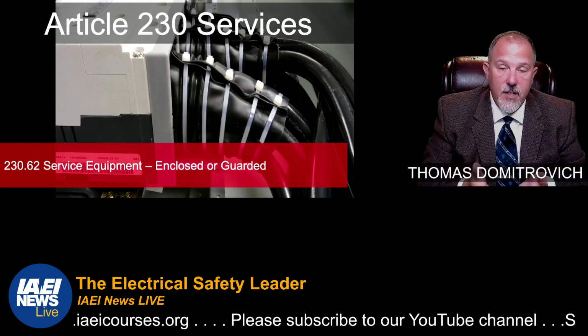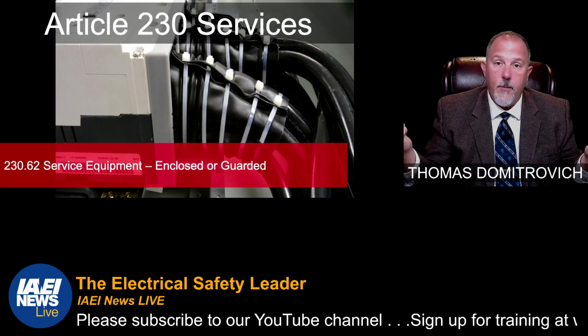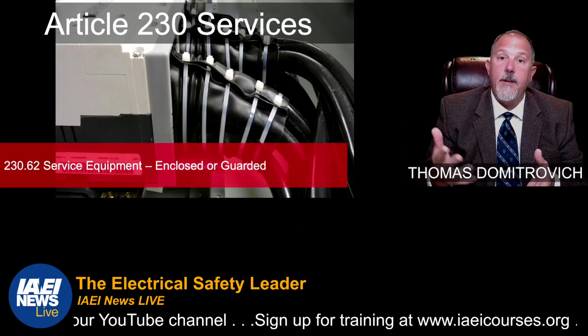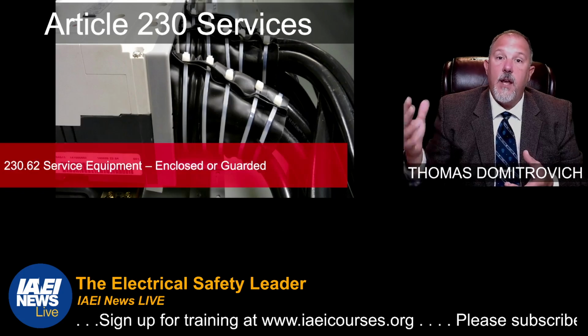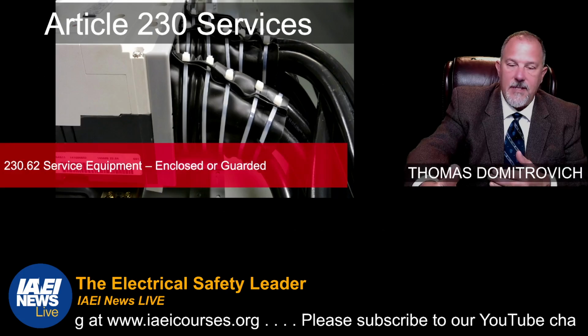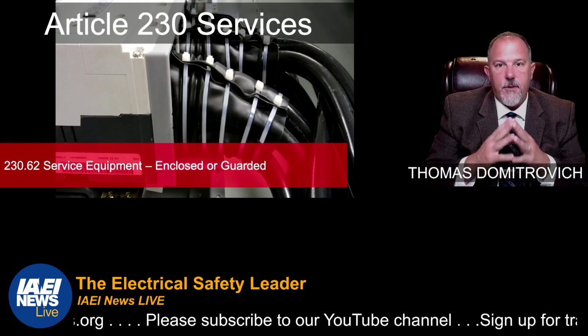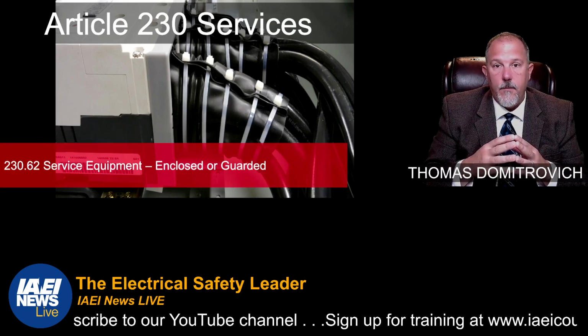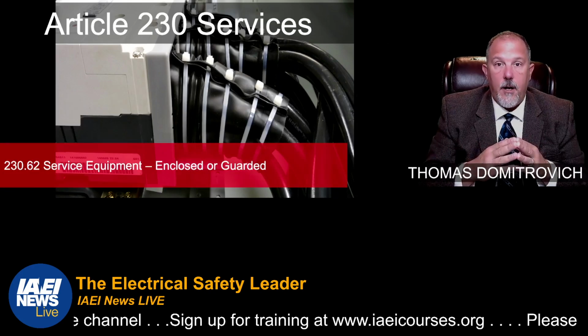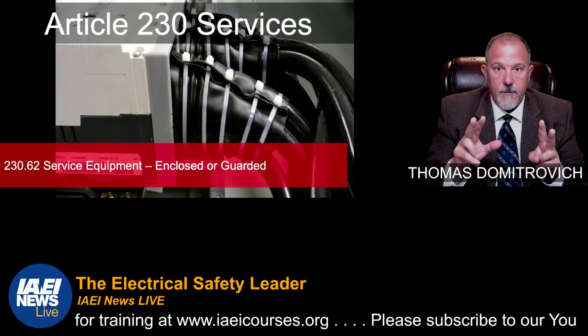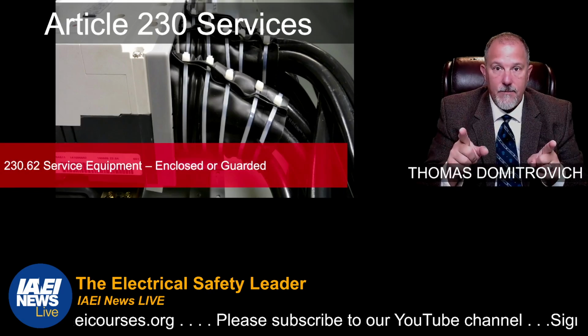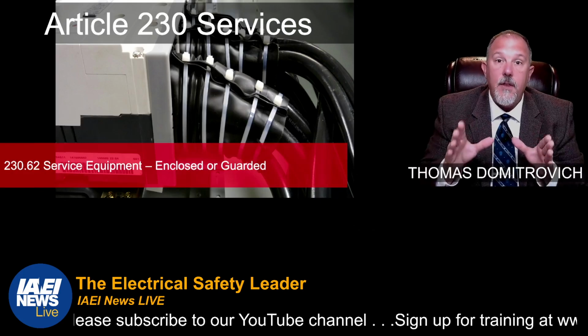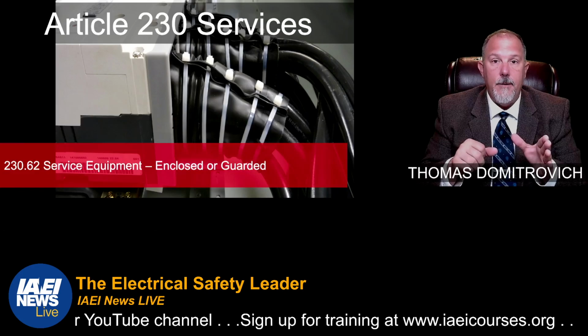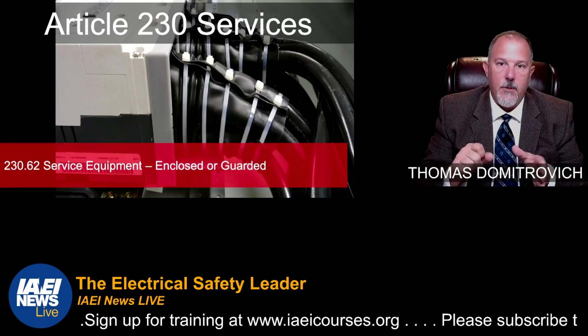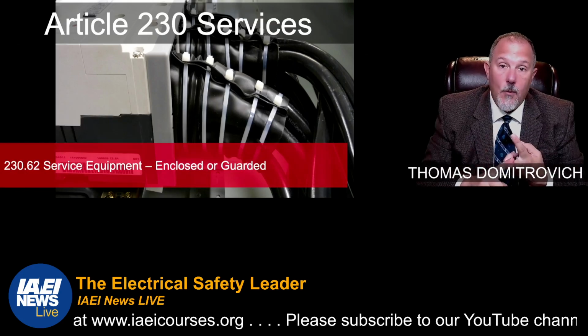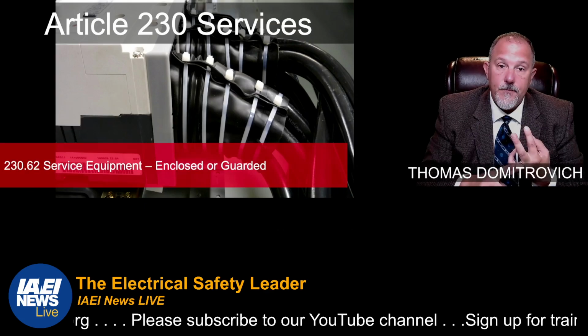because multiple panel boards are fed from a single transformer, which is permitted by the code. And maybe the other panel boards are serving emergency loads, or other loads that you can't turn off without creating an additional hazard. You know, go back to NFPA 70E. So what we did in 230, and what you're going to see in the 2023 code cycle, is we reduced the likelihood of an event from happening. Remember, risk is comprised of two things: likelihood and severity. Remember that, because you can look at everything you do through the eyes of risk, likelihood and severity. What is the likelihood that I'm accidentally going to touch something in this panel board? It may be dependent upon where you're located, the work that you're doing, how you're doing that work, all that jazz.